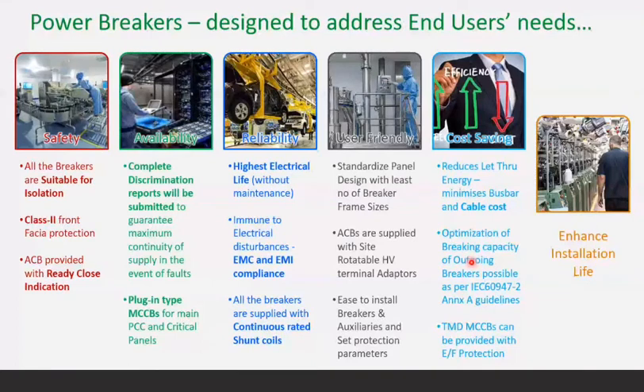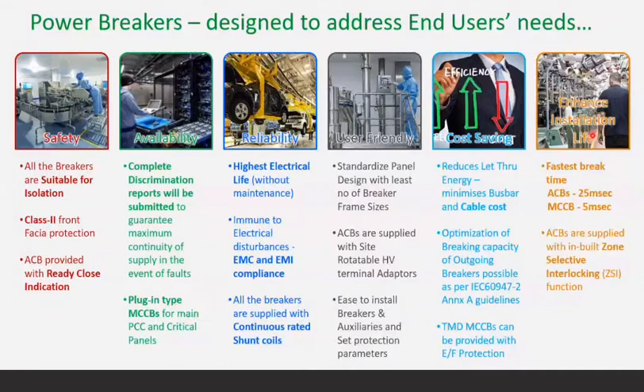Cascading can enhance the discrimination, because of which you can optimize the size of outgoing feeders. If you have total discrimination from the incomer to the final distribution level, then as per IEC 60947, we can reduce the size of a few outgoings which fall under the cascading. Then we have thermal magnetic MCCBs also, which can be provided with E/F protections. So the next point is how to enhance the installation life.